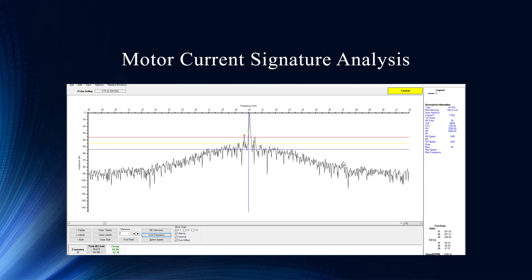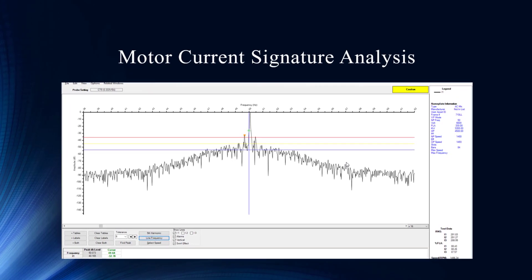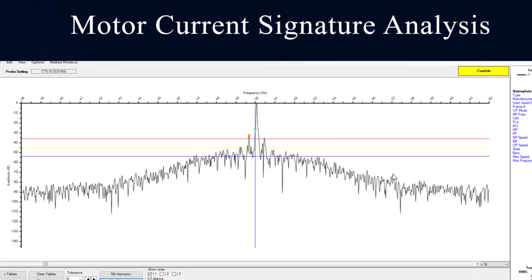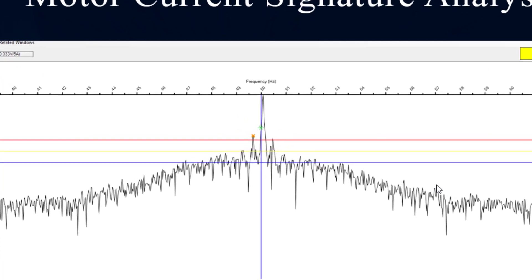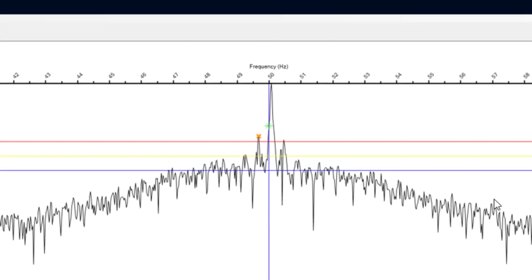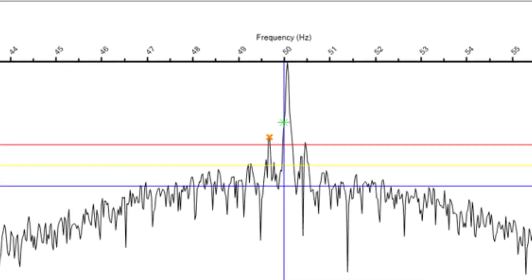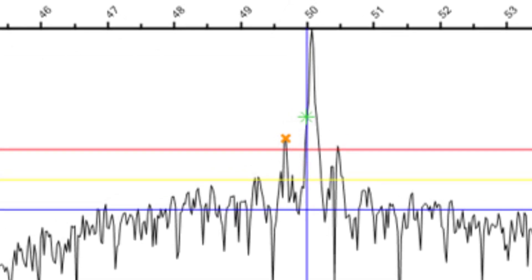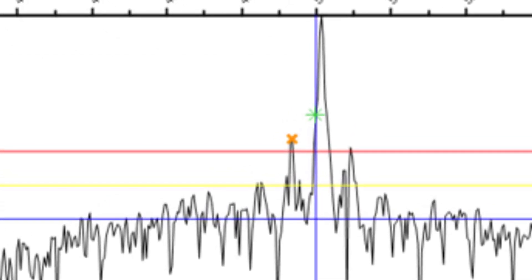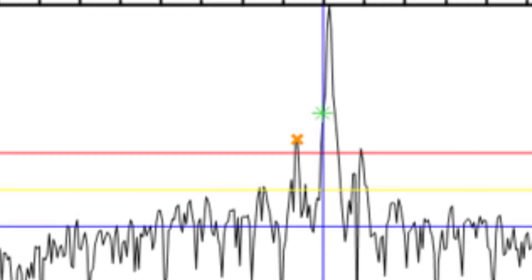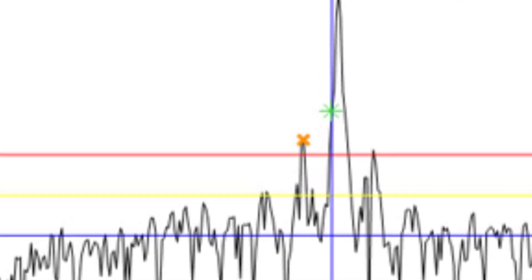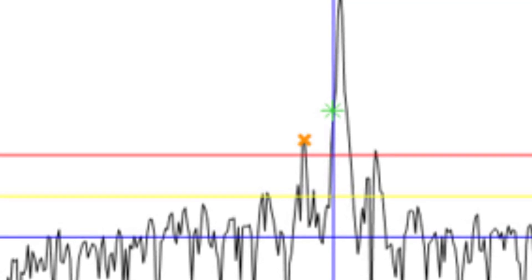Let's get into the data — the actual data portion of it. Once we've clicked on that rotor raw data for this motor, what is this telling us? This is a current signature spectrum. We talk about red being bad — we try to help out the end user or the analyst to say, hey, this is where the industry standards from a red line indicate that it's gotten too high. It's the pole pass amplitude with the red X on it, and that's basically a relationship between the rotor and stator indicating that the magnetic field is creating this peak and it is in a severe condition.